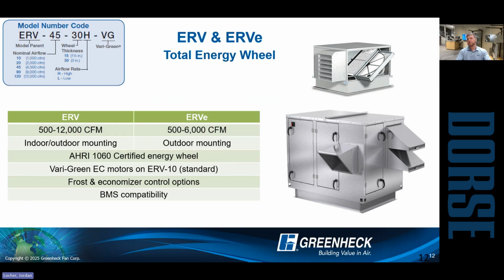On the wheel side of things, we do have two different wheel models, both the ERV and ERVE, right? So these are small to large wheel ventilators, anywhere from 500 to 12,000 CFM, right? Same thing, indoor or outdoor mounted, and these are full-on commercial units. So, just about anything you can think of, other than tempering included in the unit, right? So these are standalone ERVs. They do have the ability to control downstream heating or cooling, but we don't have full-on tempering built into these models.